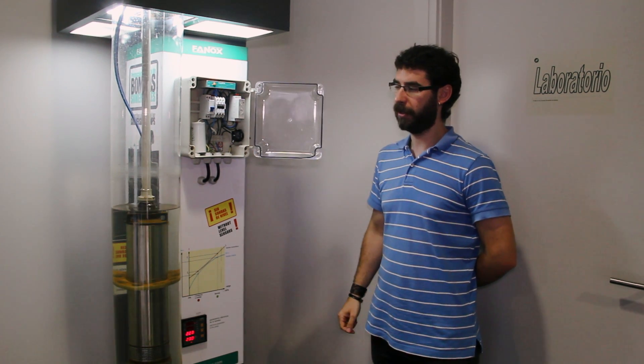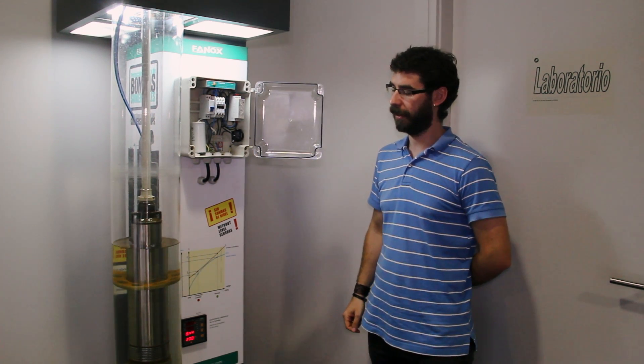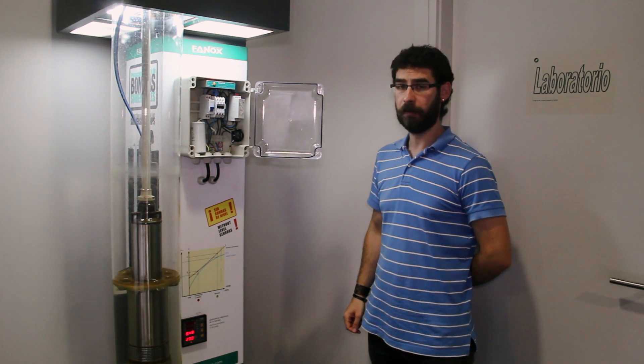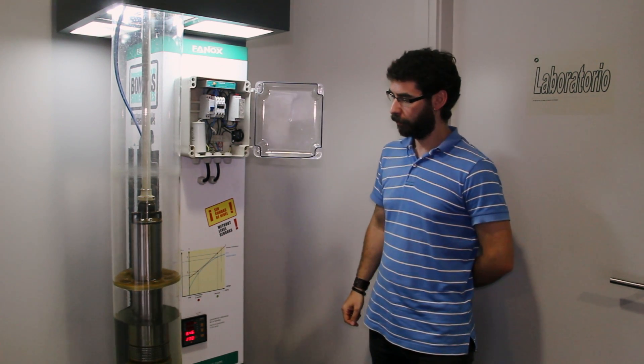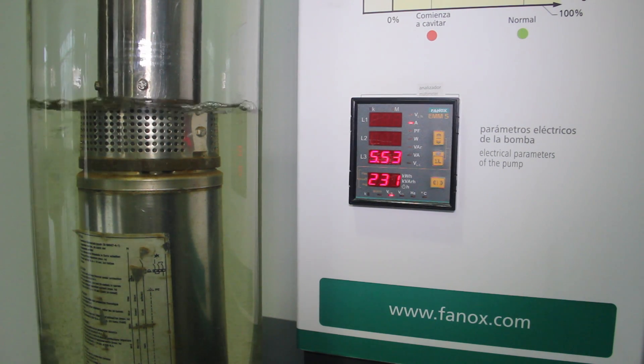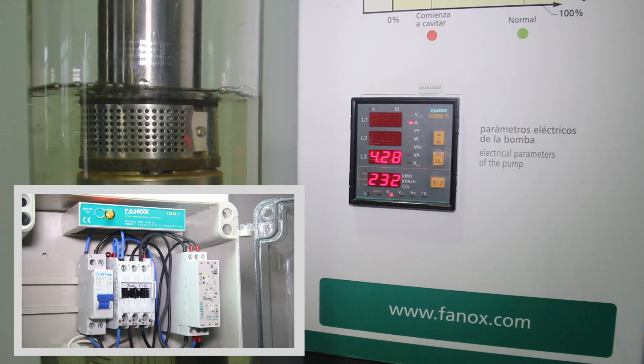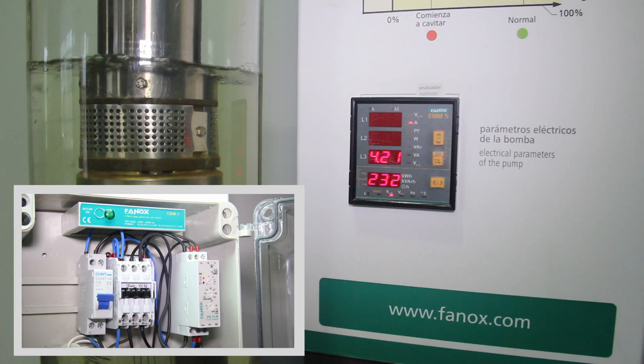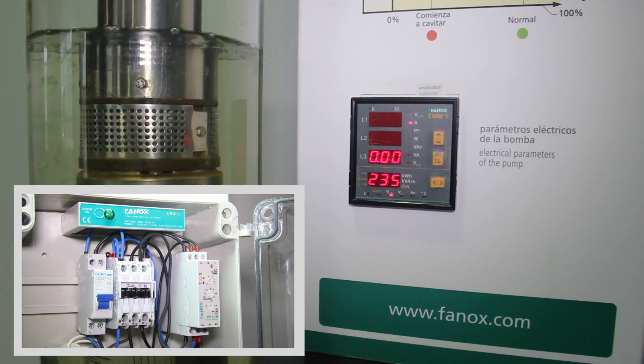We will see how the water level decreases gradually until the pump reaches the point in which it starts to work with no load. We will also see how the pump's consumption cuts down from 5.5 amperes to 4.2 amperes.